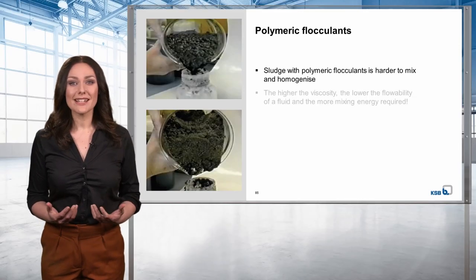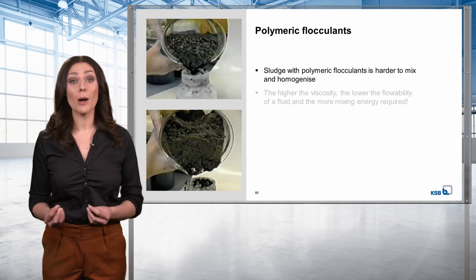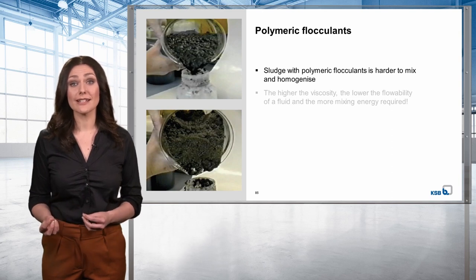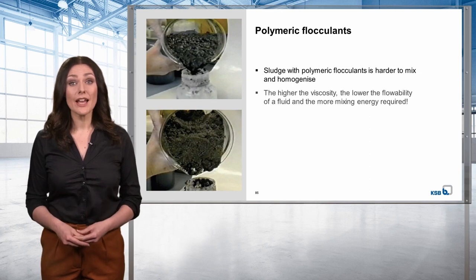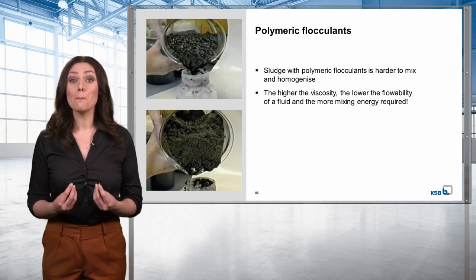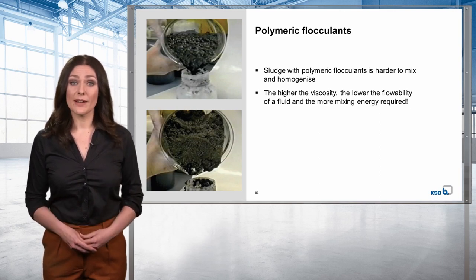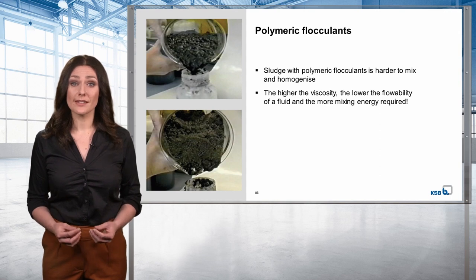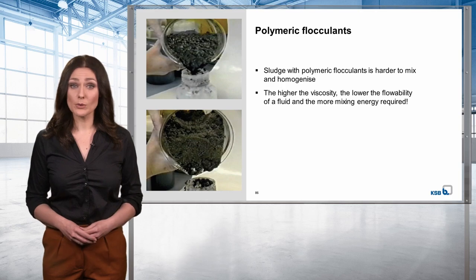When selecting a mixer, it has to be taken into account that sludge with polymeric flocculants is harder to mix and homogenize. This means the higher the viscosity, the lower the flowability of a fluid, and the more mixing energy required. For this reason, it is of major importance that you know the DS content, the thickening method, and whether polymeric flocculants are used.